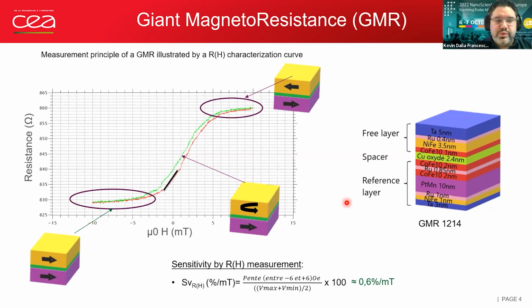Two other important things to note. The first is that the development of the GMR stack is more complicated than two layers, as shown in this diagram of the GMR used. And the second is that the sensitivity is important because it allows us to go from the resistance measurement made by the GMR to the stray field value.